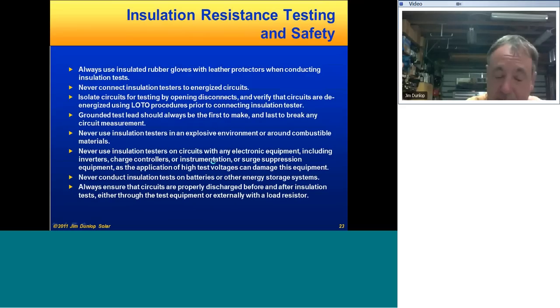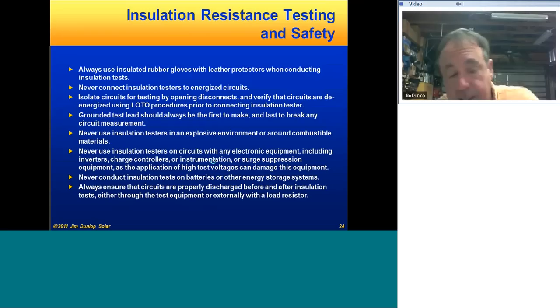A lot of safety issues with the insulation resistance tester. They put out high voltage, some of them several thousand volts, depending on what kind of conductors you're testing. So you should be wearing gloves. You always make sure circuits are de-energized with the exception of the array. Isolate all the circuits.